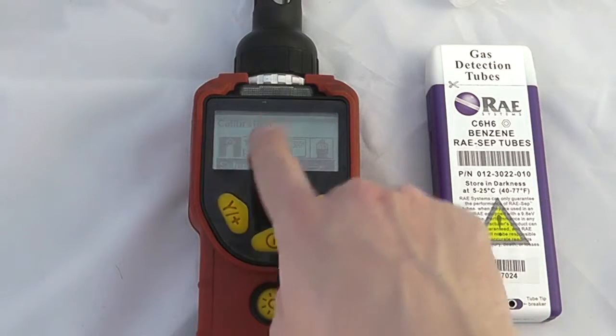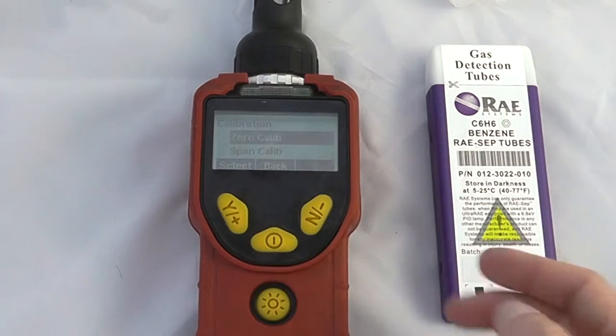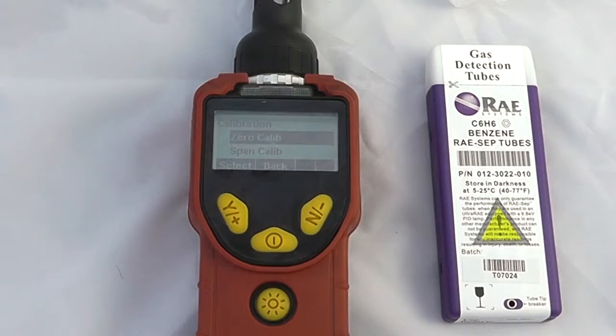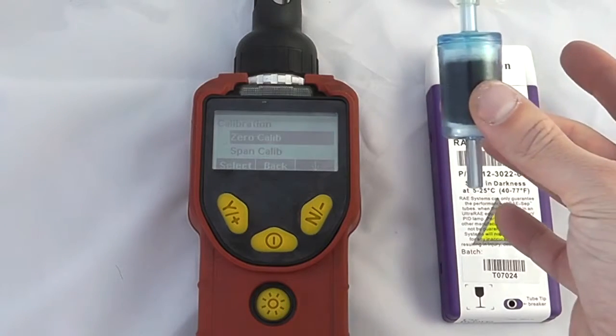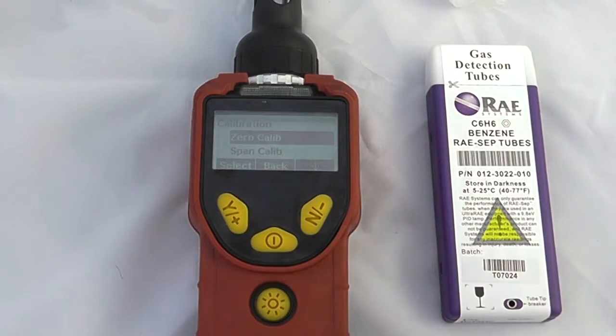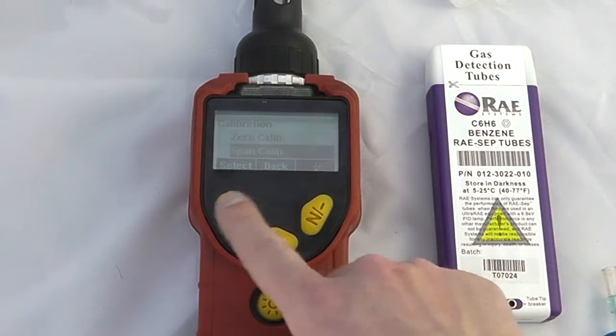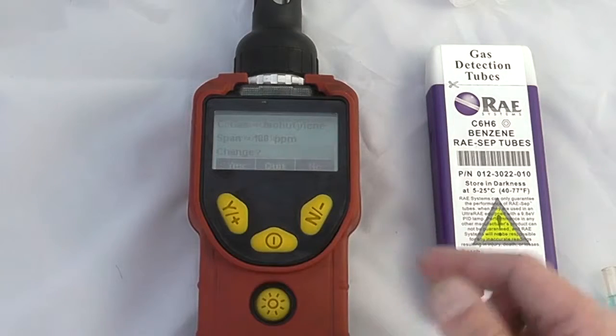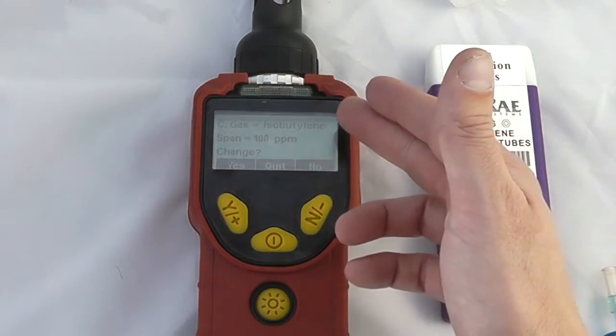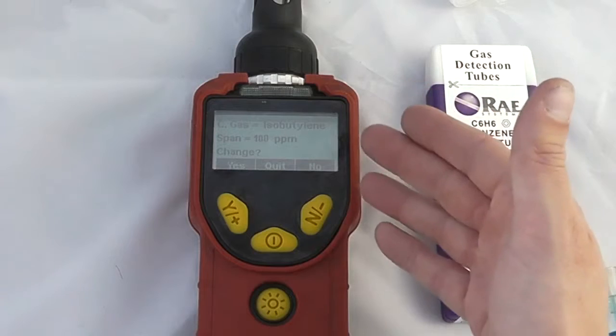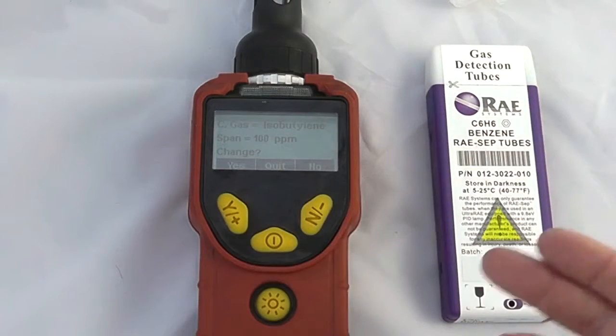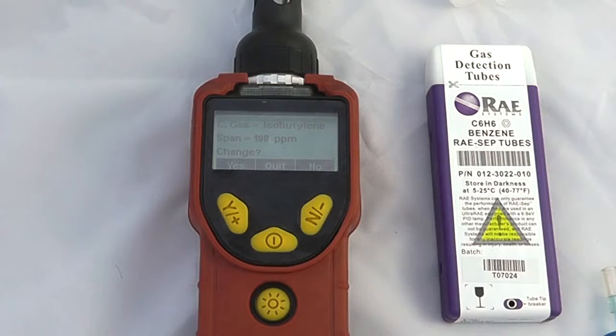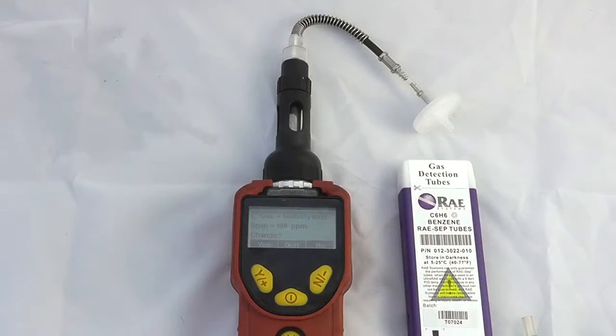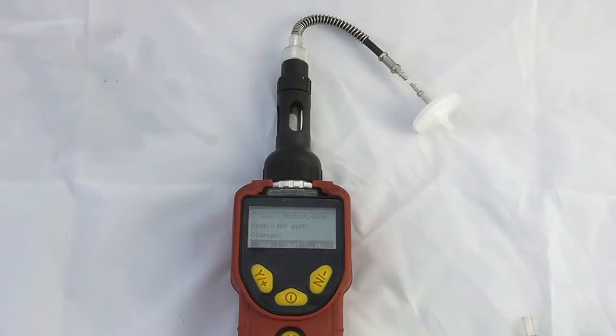So the options, firstly in the calibration menu, we can start up calibration. We can do a zero calibration, which means we can get a baseline zero value, again using the carbon filter. In this case, because I did a zero at startup, I'm not going to go through the zero calibration function. We can then do a span calibration. Now we can calibrate with either isobutylene for general VOC measurement, or we could potentially calibrate with benzene at 5 parts per million. I happen to have a can of isobutylene with me, so I'll just remove the tubes.